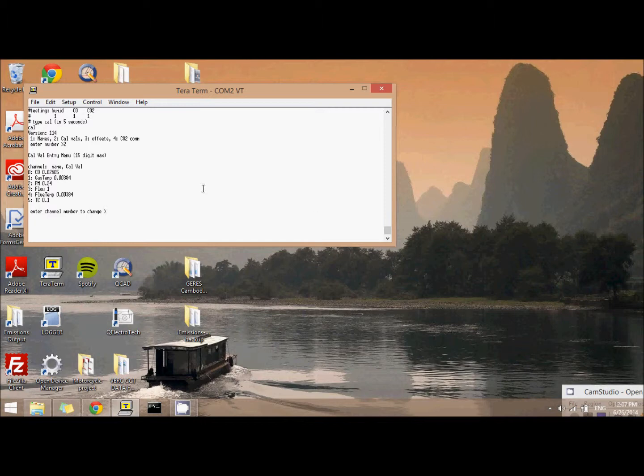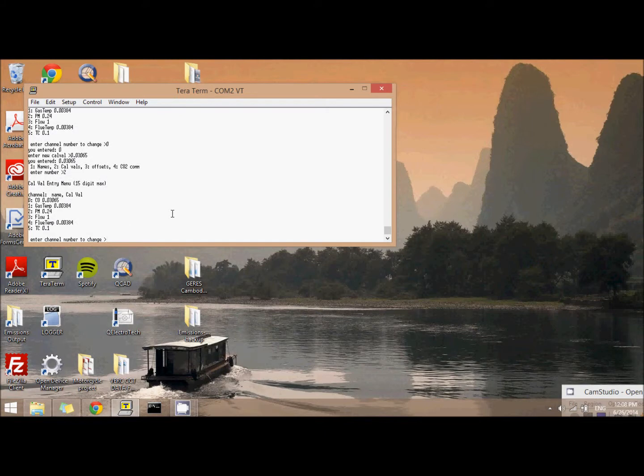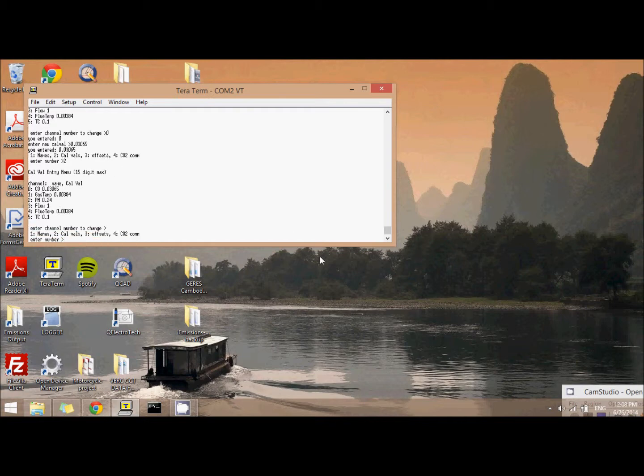All I'm interested in though is channel 0, the CO channel. So I'm going to enter 0 and press enter, and that gives me a chance to change the CO, the carbon monoxide calibration value. So for this example, I'm going to enter my new calibration value. This is going to be different for you, so just enter whatever you calculated in the last section. I hit enter, and that's it. I can check the menu again to see if it entered correctly. So I go back to menu 2, the calibration values, and hit enter, and there I see my new calibration value for the CO in channel 0 right here at the top. That looks good, so I'm ready to go on to my next part, entering the offset. So to end, I just click enter instead of a channel number, and that gets me back to the main menu, ready to enter the new offset.